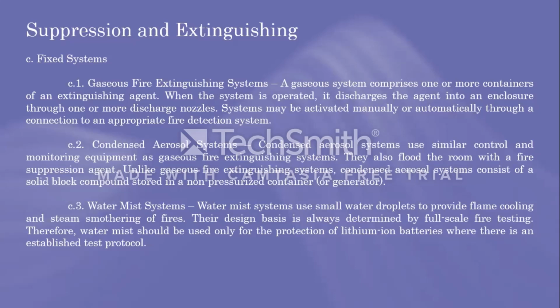Condensed aerosol systems. Condensed aerosol systems use similar control and monitoring equipment as gaseous fire extinguishing systems. They also flood the room with a fire suppression agent. Unlike gaseous fire extinguishing systems, condensed aerosol systems consist of a solid block compound stored in a non-pressurized container or generator. So number 3, water mist systems.